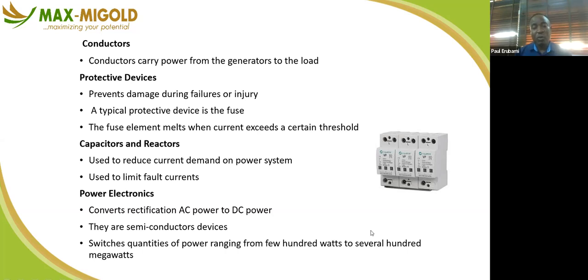So when the fuse is supposed to cut off, when there is an abnormality, when there is a problem or a surge, the fuse will still tolerate it because the wire is overrated. It's tolerated. Before you know it, it will set your house ablaze. It results in a fire incident. That's why in most houses, when you ask what's the cause of this fire, nobody can really trace what happened. It's because you got one electrician from the roadside to come and give you light. So we have deviated from using fuses to using circuit breakers. We'll get there. I will explain circuit breakers to you in detail.